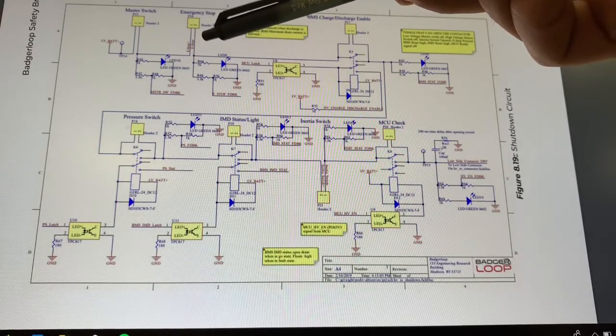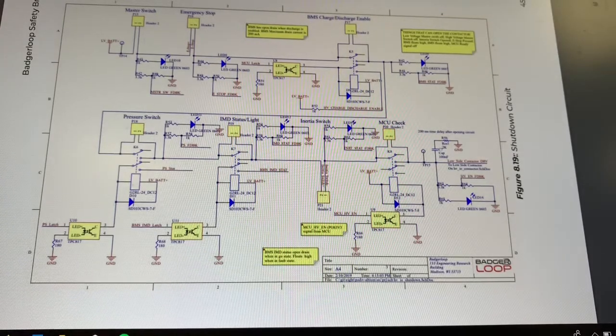Next in series on the circuit is our emergency stop. This is simply another switch we have at the front of the pod, directly in series with the circuit, that if pressed will open the circuit and effectively open the low side contactor, turning off the battery.